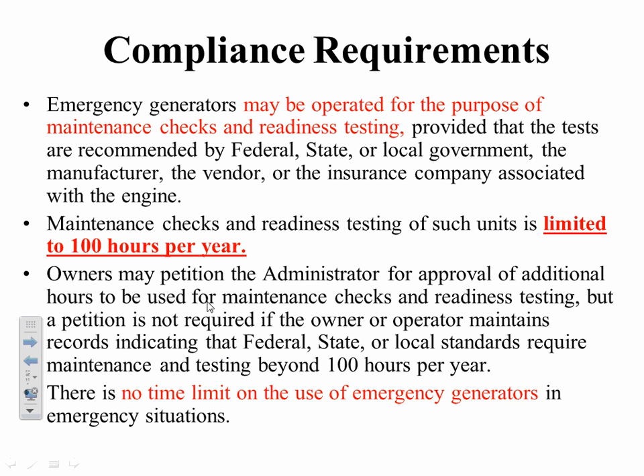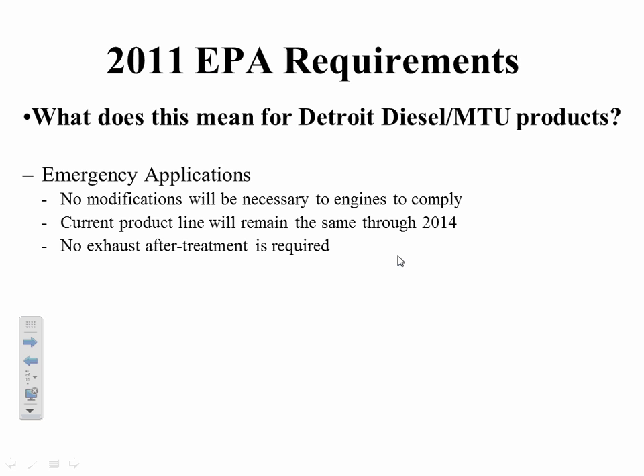And if owners don't like that, they can petition for a change. But there's no time limit on the use of emergency generators in true emergencies. So anytime the power fails, you can run it. There's no limit on those hours. So Jerry, if you have a data center, you lost the power, you call your data center, would that qualify as an emergency? Yes.